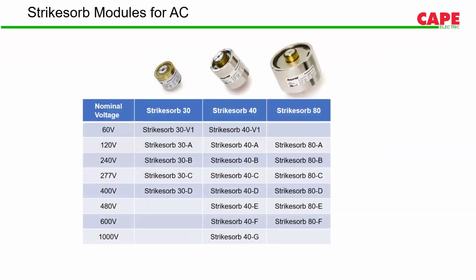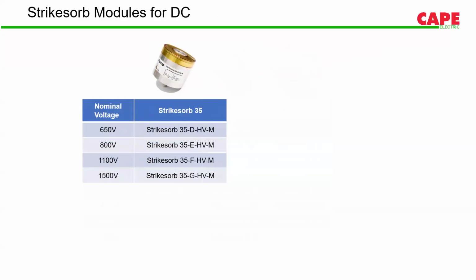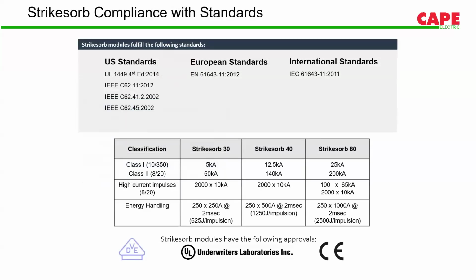metal oxide varistor. So there are multiple models, Strikesorb 30, 40 and 80, with multiple impulse currents and maximum discharge currents: 60 kiloamperes for 30, 140 kiloamperes for 40 and 200 kiloamperes for Strikesorb 80. We have multiple voltage ranges, 60, 120, 240 to 277 volt. We have various models A, B, C, D, E, F and G in the Strikesorb series. Then we have the Strikesorb DC series also, the Strikesorb 35 series.